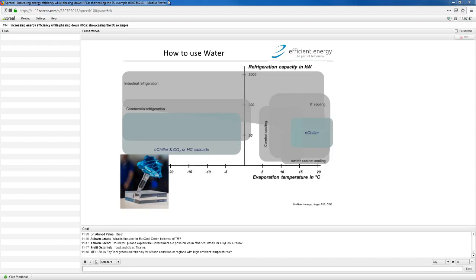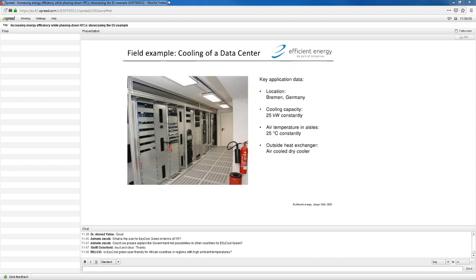In the worst case, if you've got a cascade with a brazed plate heat exchanger between water and CO2, it never gets worse in the case of the failure of the heat exchanger—it never gets worse than that you got sparkling water instead of water, but that's it. So what we did is, as one of the examples, we installed the system in 2014, which is after all five years ago, more or less.